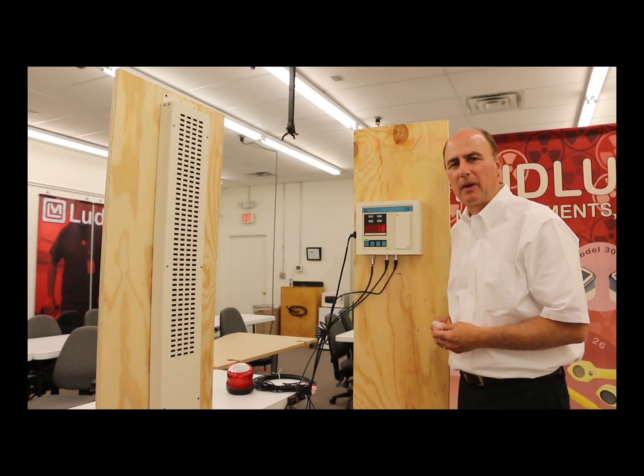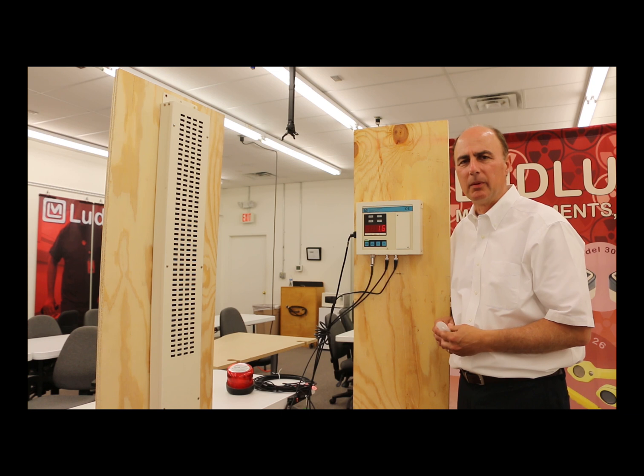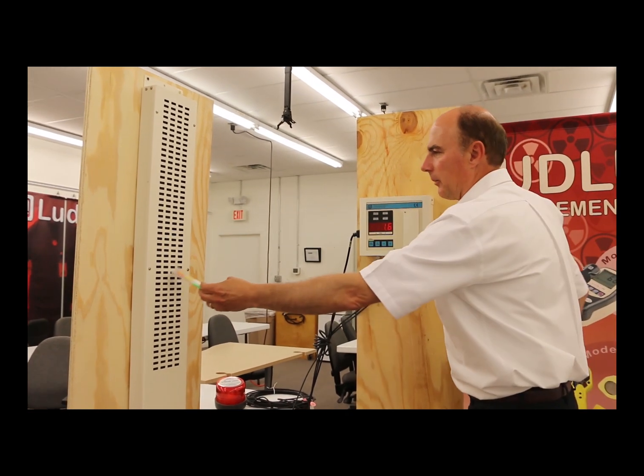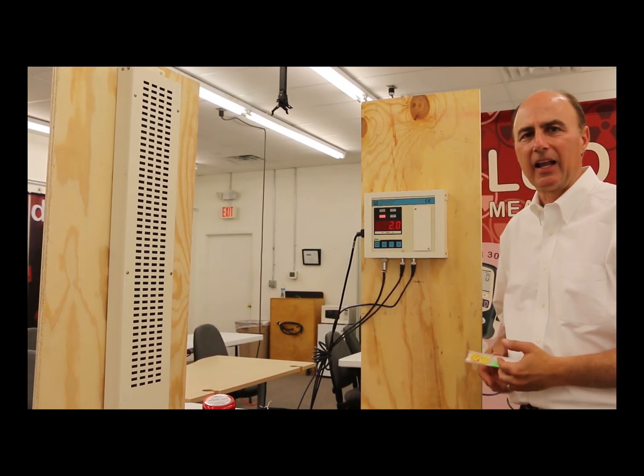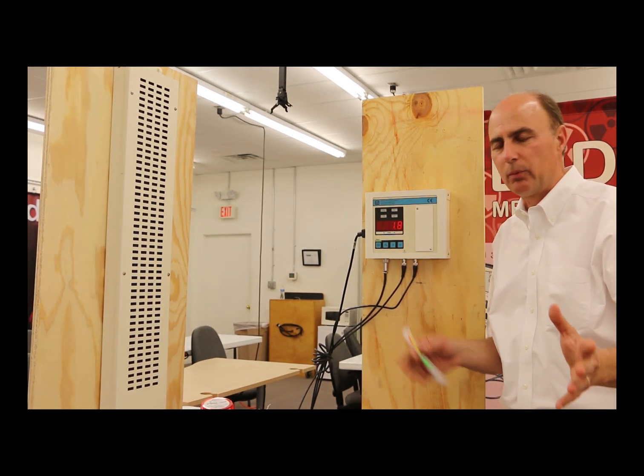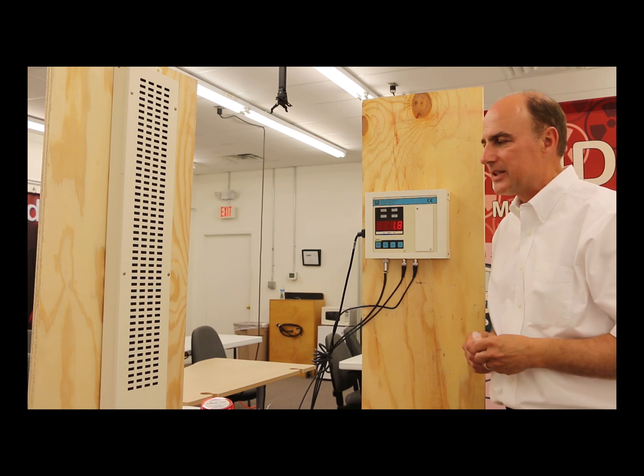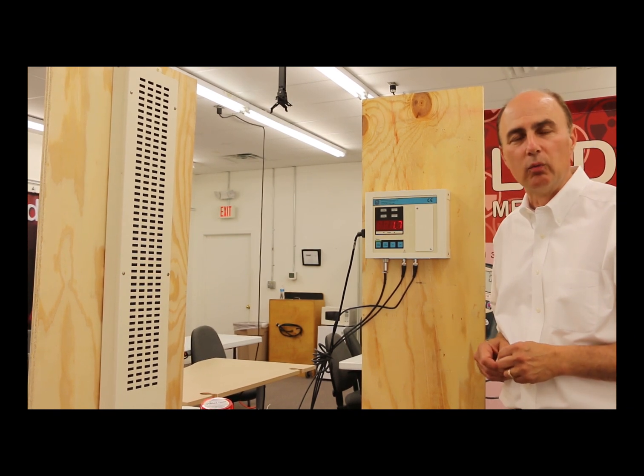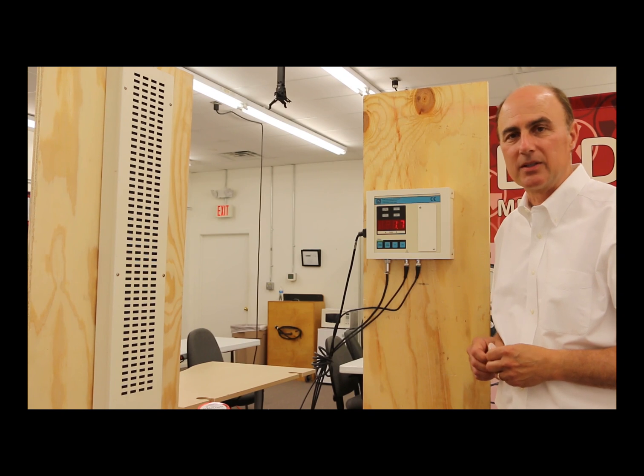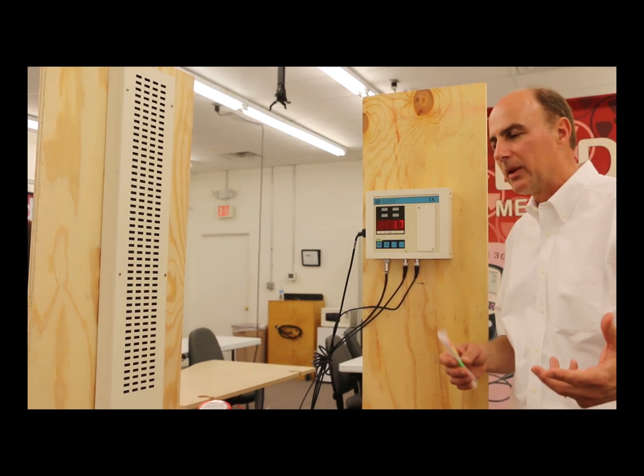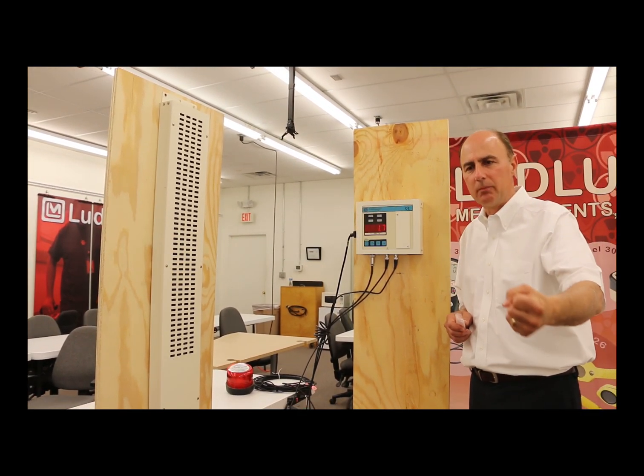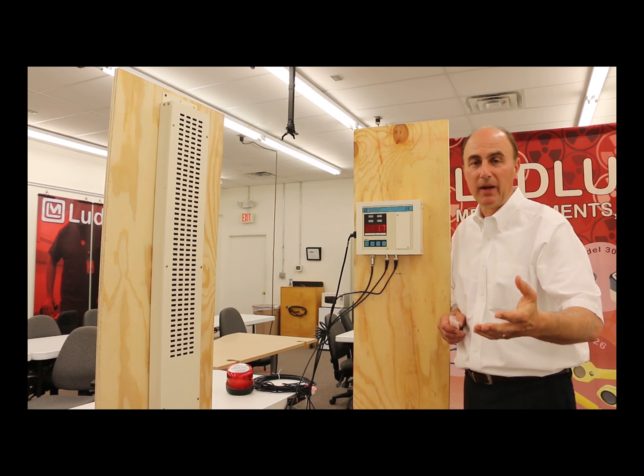So the last thing I want to talk about is response. Your response to alarms are going to vary from location to location and depending on your needs. But in general, people respond to these similarly. So I get an alarm. We decided in this case it's a non-latching alarm, but the alarm goes off. Someone was moving waste by the portal monitor and they got an alarm. Typically what happens at that point is that waste container that you were wheeling by, you know that there's a bag or two of waste in there that's got radioactive material that we can sense. And so at that point, normally they back away into the dirty side of the portal, we want to call it that, and we'll take bags out one at a time, move it through the portal to find which bag or bags is offending.